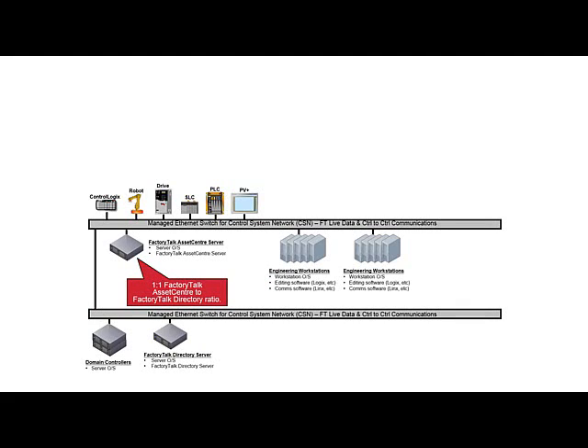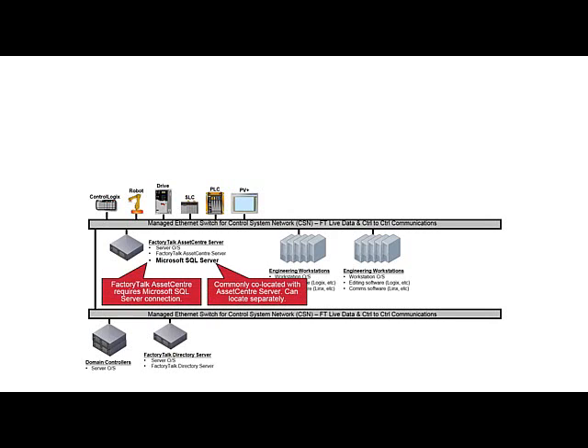The next component is the FactoryTalk Asset Center server. Each FactoryTalk Asset Center system will have one single Asset Center server. It is important to note that there can only be one FactoryTalk Asset Center server per FactoryTalk Directory Server. Likewise, a single FactoryTalk Asset Center server can only exist within one FactoryTalk directory — it cannot service multiple directories at the same time. The Asset Center server will require a Microsoft SQL database hosted on a Microsoft SQL Server.